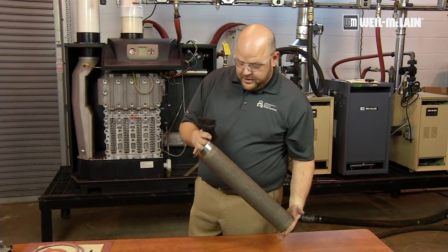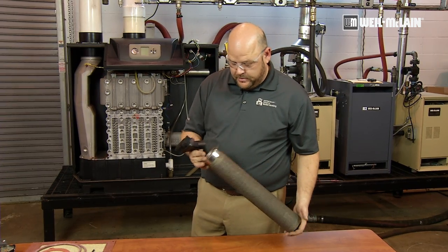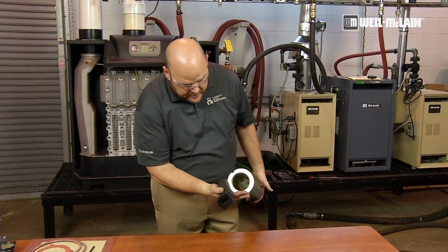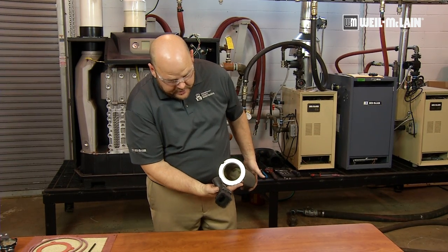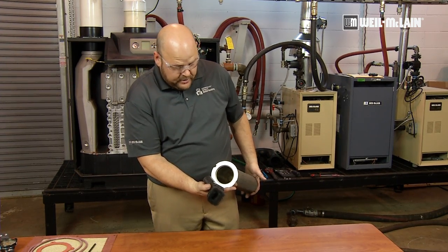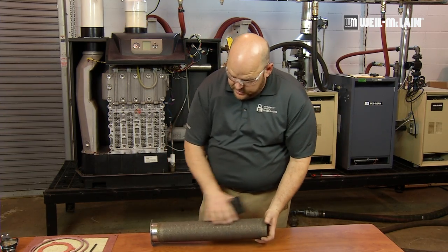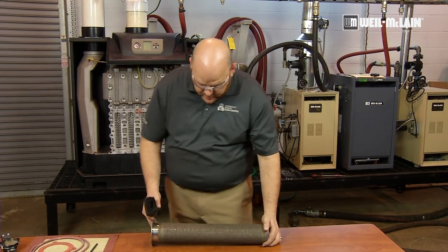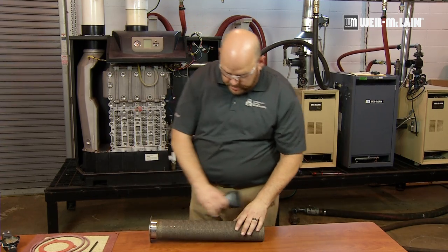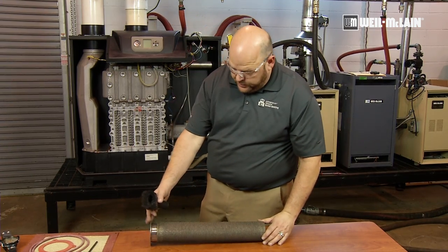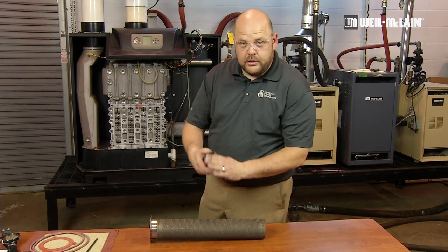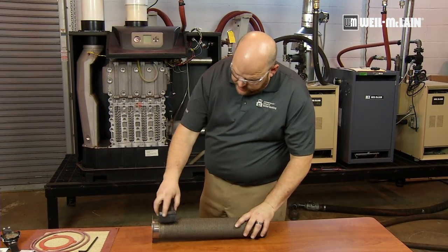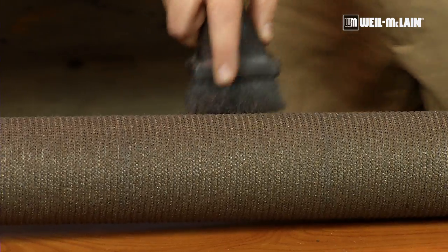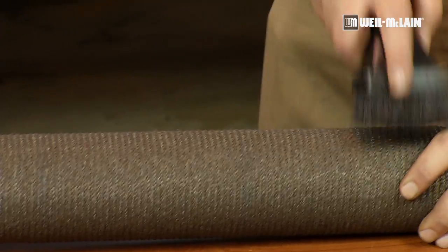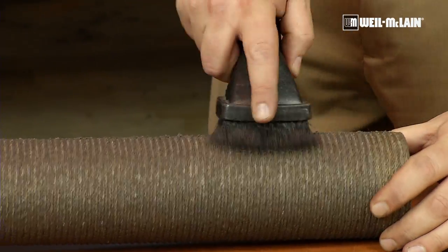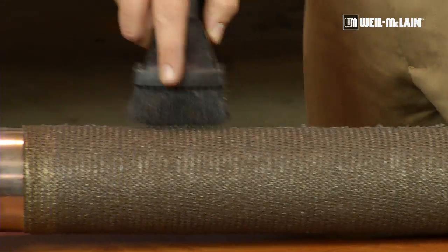This is our burner that we use in the SlimFit boilers. It has a rigid stainless steel core and then is wrapped by a stainless steel mesh. It doesn't look to be dirty, but you will get debris and so forth inside the mesh. Using a soft nylon bristle brush, you're going to want to brush down the burner, rotate and continue brushing until we can get all the way around. You can also use a vacuum.